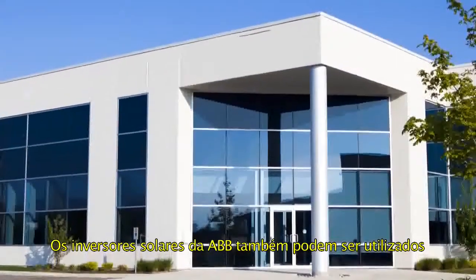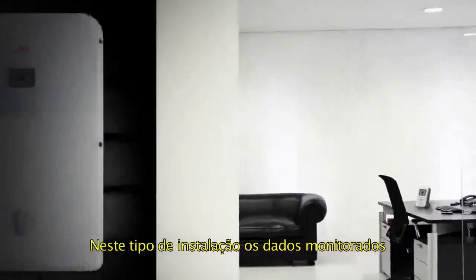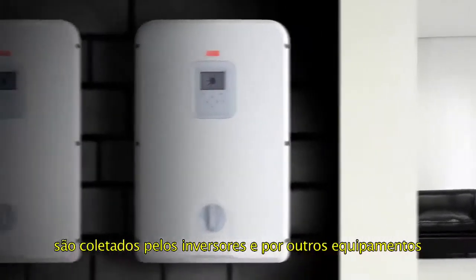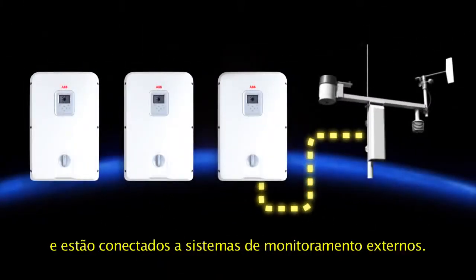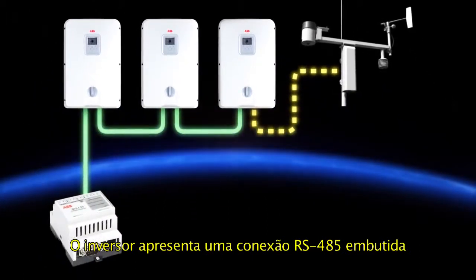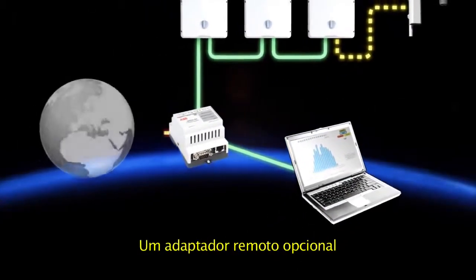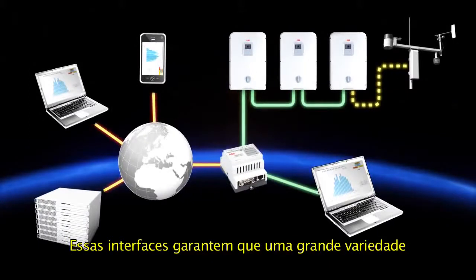ABB string inverters are also suitable for larger installations, such as commercial buildings. In this type of installation, monitored data is collected from inverters and other equipment, such as weather sensors, and is connected to external monitoring systems. The inverter features a built-in RS-485 connection with Modbus communication. An optional remote monitoring adapter provides Ethernet connectivity. These interfaces ensure that a wide range of data communication options can be implemented.